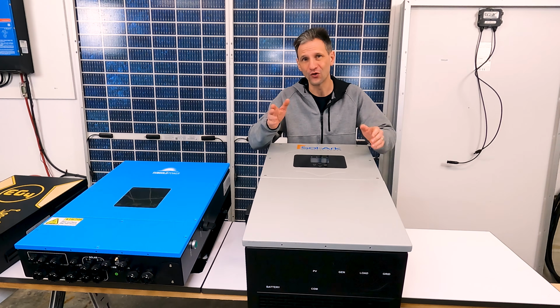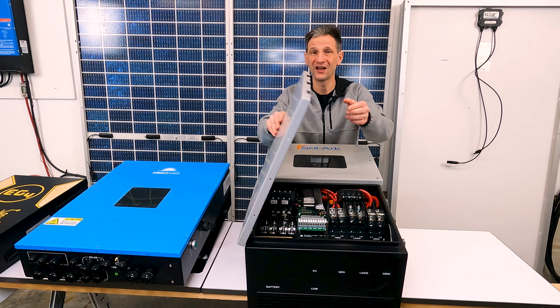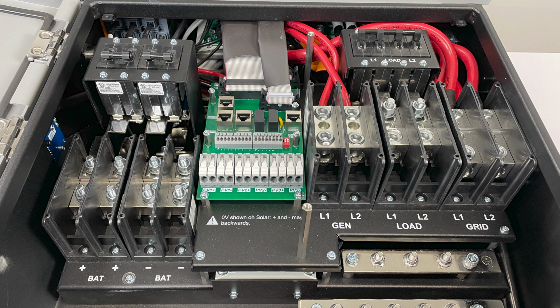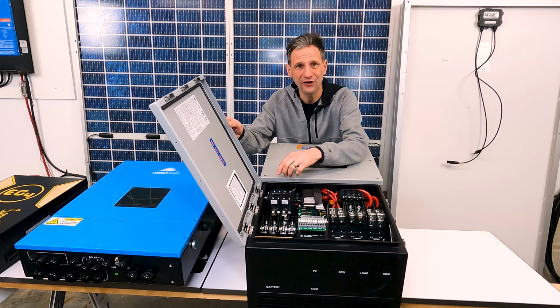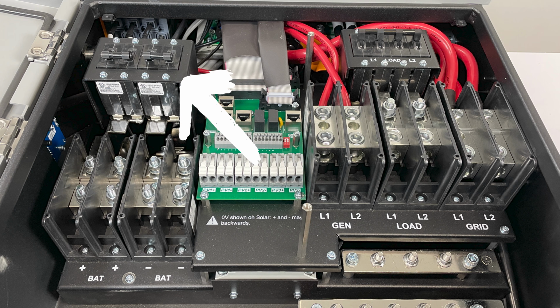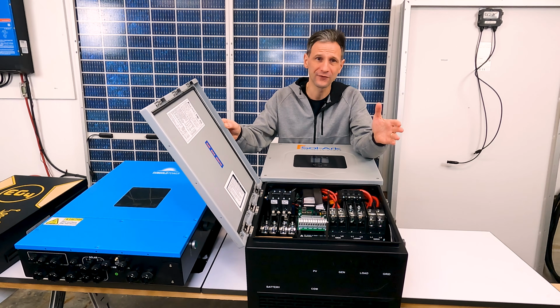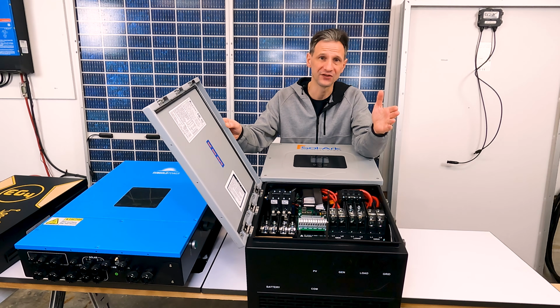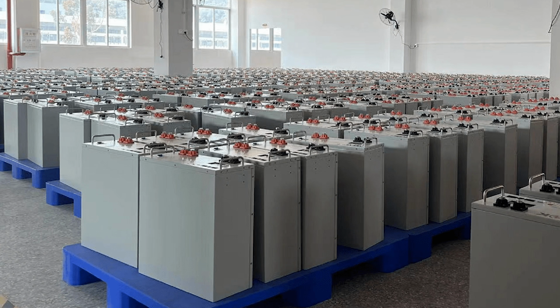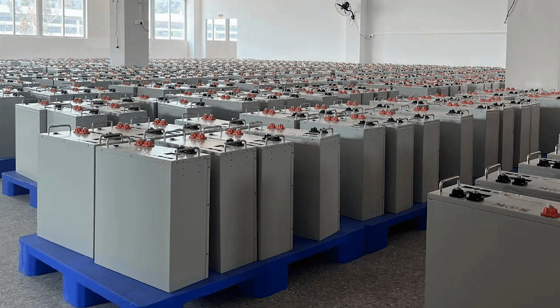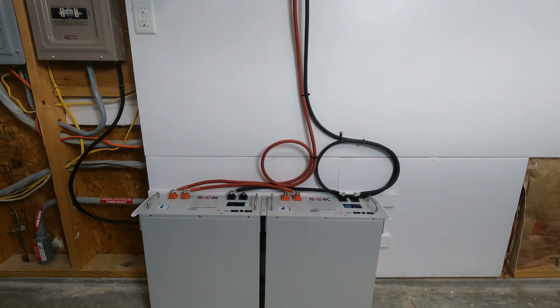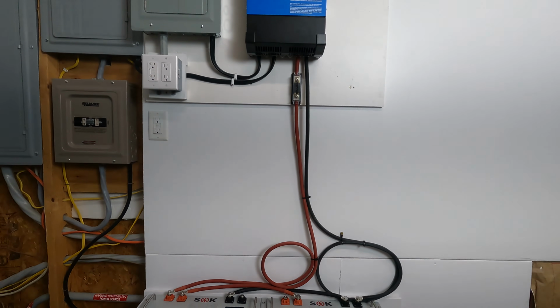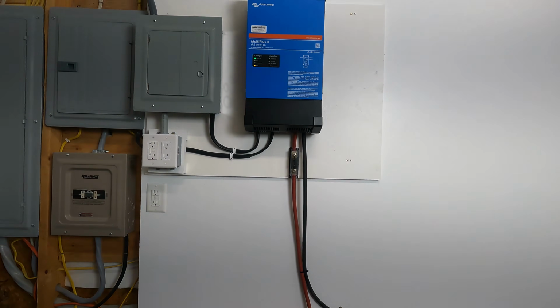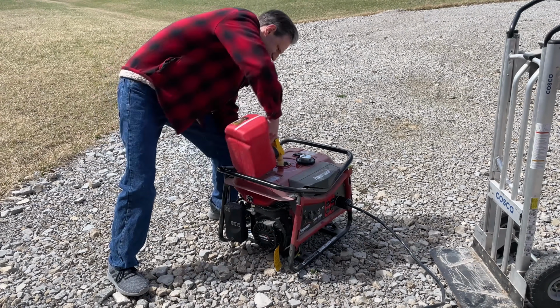This unit also has 2 AC inputs, but they're at another level. With integrated breakers and very nice lug-style connectors, even the battery input has an integrated breaker. This unit is sufficient to be a transfer switch and power management system for an entire typical house. In a power outage, it can charge the batteries and run the house with PV. And if the batteries get too low, it can automatically start and stop a generator for supplemental AC input.